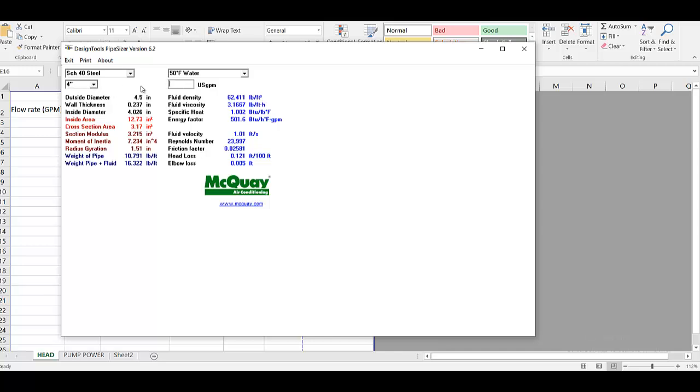So how can we select? First of all, as you know, from fixture units we can calculate the total flow rate, the GPM in the main pipe, that is, the pump flow, the total GPM. So in the first step we will add all the fixture dwelling units, and from them we will find the total GPM, and here we can write the total GPM. Let's suppose the total GPM is 400 US GPM.